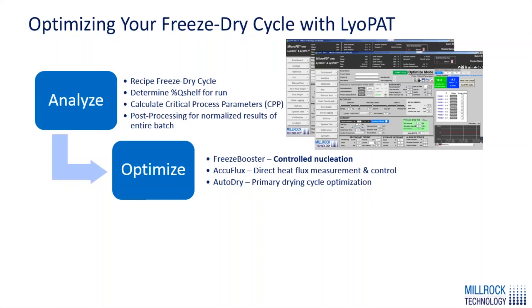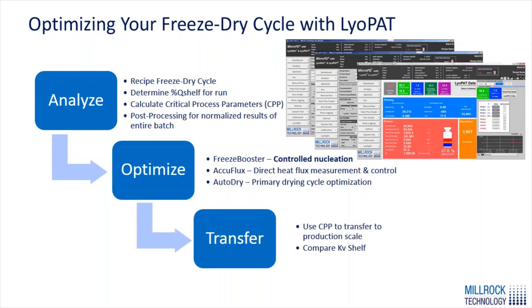Using these three optimization features, we optimize our cycle to develop a better, more uniform cake across the batch and reduce the cycle time as much as possible. Once we have this optimized protocol, we can look to transferring it using the critical process parameters we've calculated, and by comparing the Kv values between various units we're looking to transfer to.